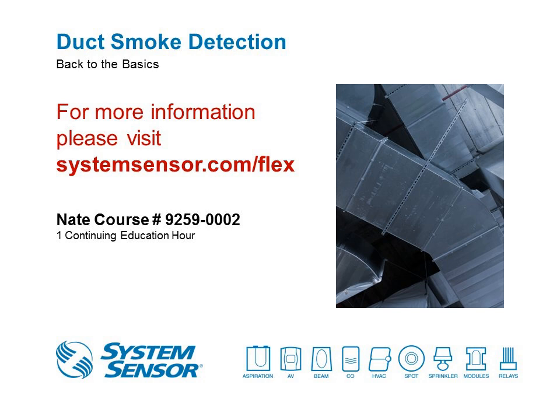Okay, all right. They're asking some code clarification. They thought you said that the IMC wants detectors in the return, and yet NFPA 90A wants them in the supply. Which location should they use? That is correct. The International Mechanical Code requires them to be in the return. NFPA 90A requires them to be in the supply. That's why we referenced that if you have a question on the local municipality, you need to find out what's being enforced in your jurisdiction, because they may be designing to International Mechanical versus NFPA.